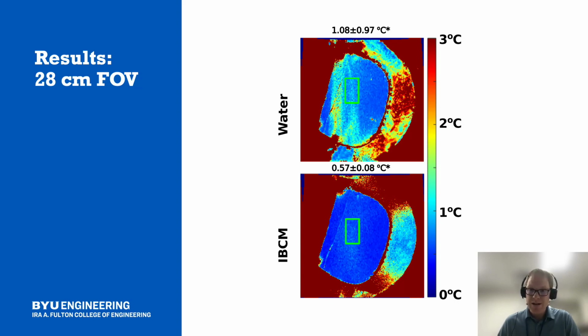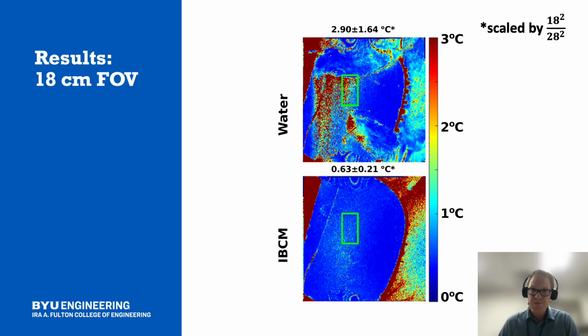When the circulating water is replaced with a circulating iron-based coupling medium, these motion artifacts disappear and the temperature uncertainty only varies with the natural B1 transmit field inhomogeneity that's inherent to this transducer design. Finally, when we shrink the field of view from 28 centimeters to 18 centimeters, aliasing from a circulating water coupling medium significantly worsened the estimate of thermometry precision. However, the circulating iron-based coupling medium, because it exerts very little signal, does not contribute aliasing and motion artifacts that degrade the thermometry precision estimate.